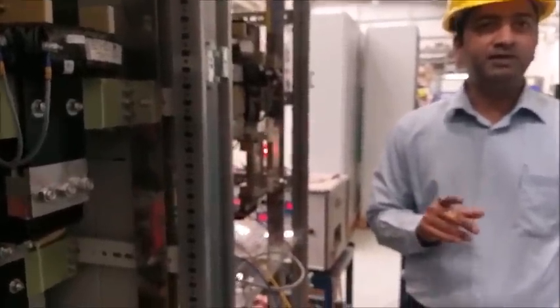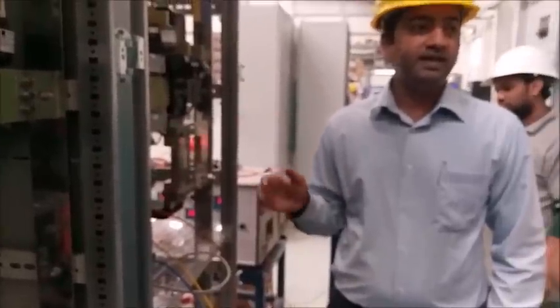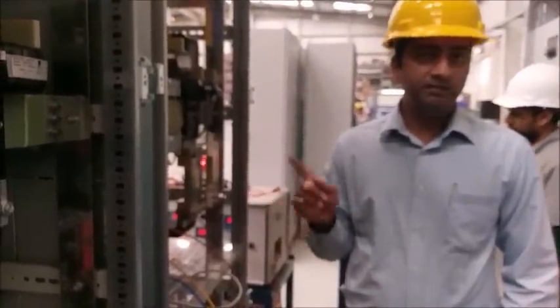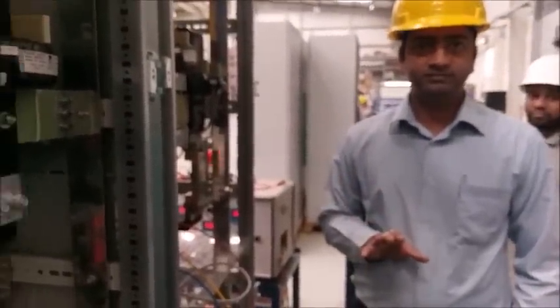Now what is the difference between Megger and HV? HV is an AC voltage, and in the Megger it is a DC voltage, because of the insulation. But the dielectric test is AC, 2.5 kV.